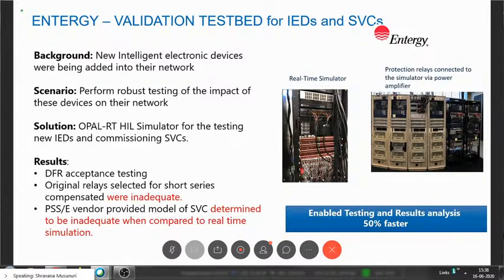But over a period of a few years, multiple things happen - regular wear and tear of the machine and controller, and continuous changes in the network. From a power systems perspective, the network architecture might remain the same every 3-4 years, but new devices or technologies keep getting added. So we cannot be sure that the initial tuning done by the vendor at installation and commissioning still holds good even after 5 years, because of continuous variability.